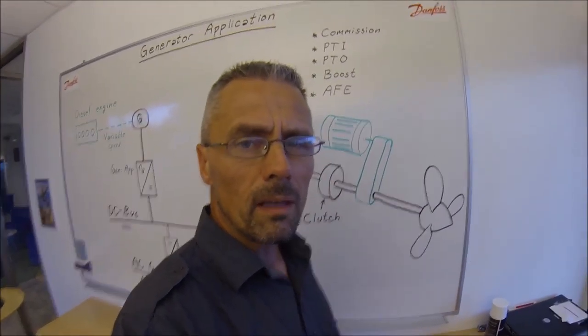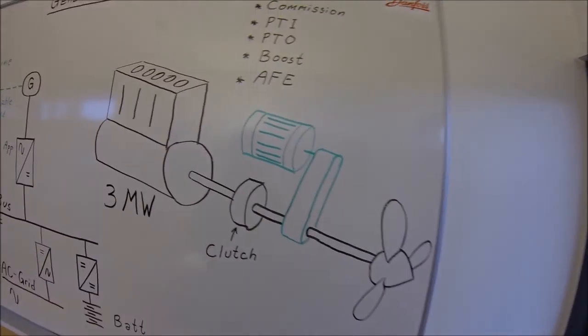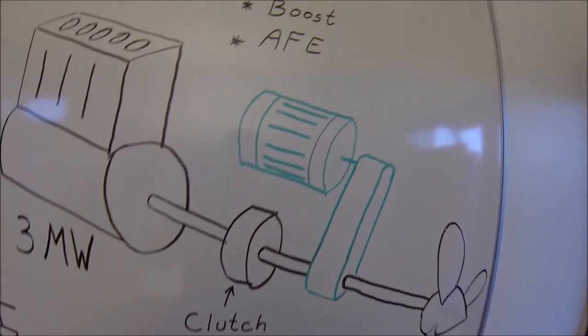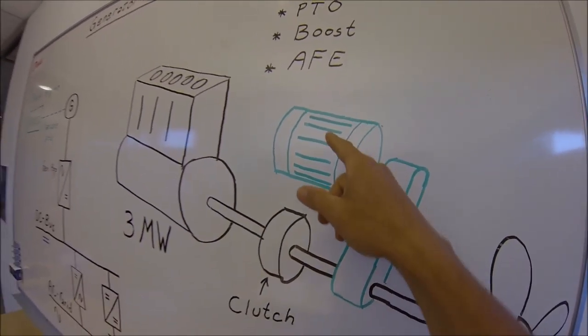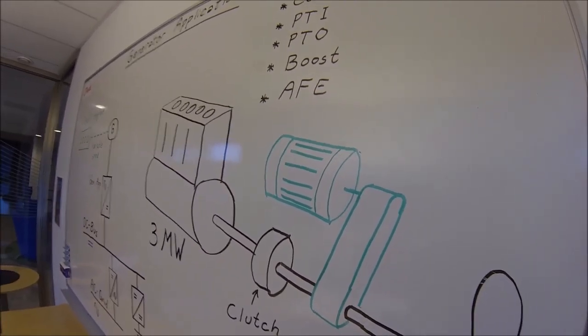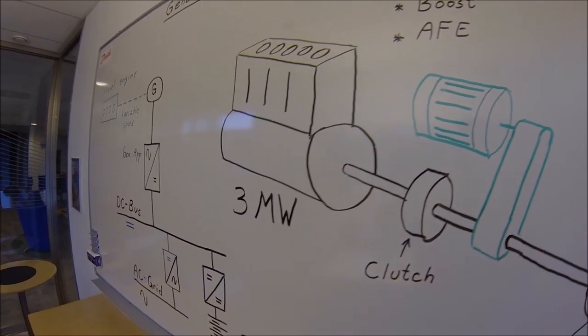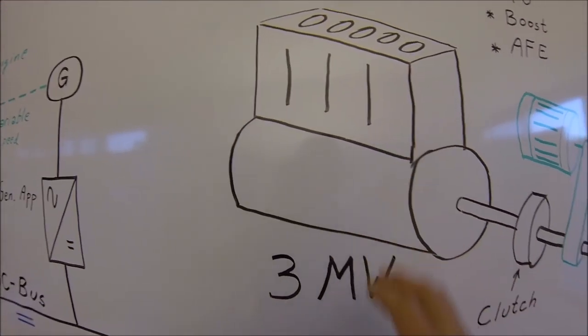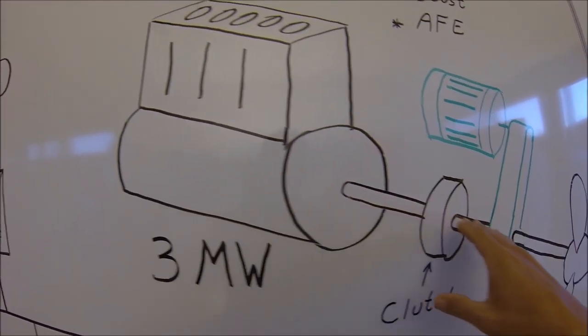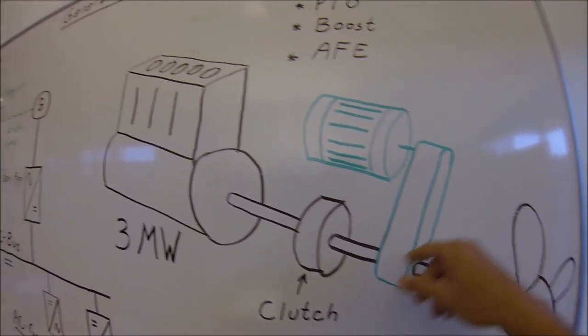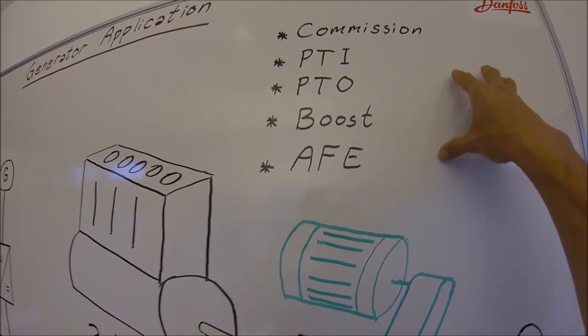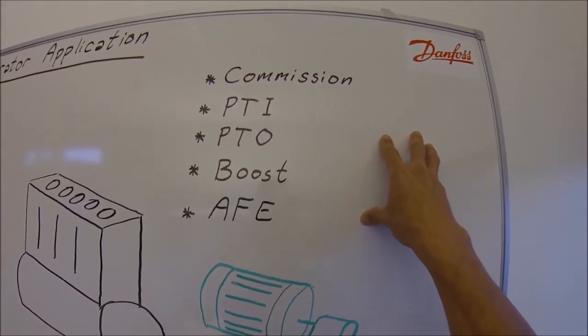The two main advantages with the generator application is that it's bi-directional. You can then use your generator as a diesel electric motor. The other one is that the big diesel engine can now use a wide range of RPMs and you still can extract energy to your 60 hertz ship grid.